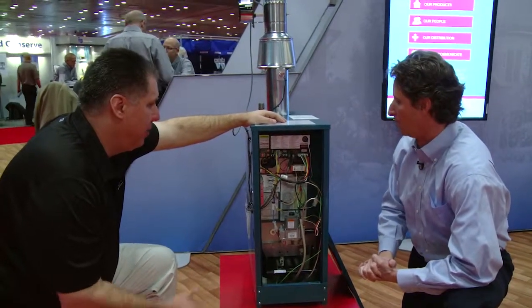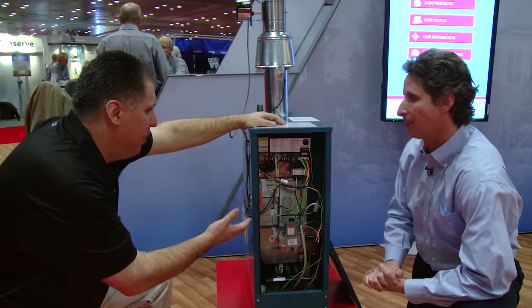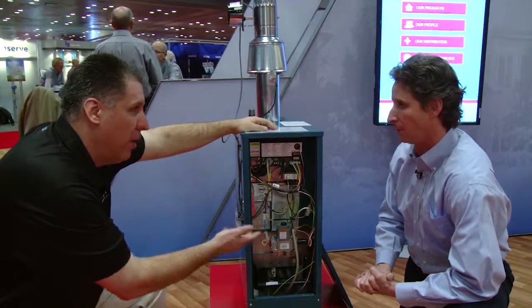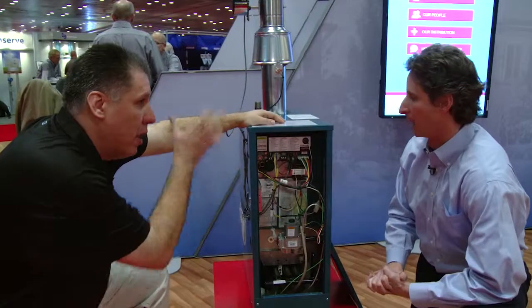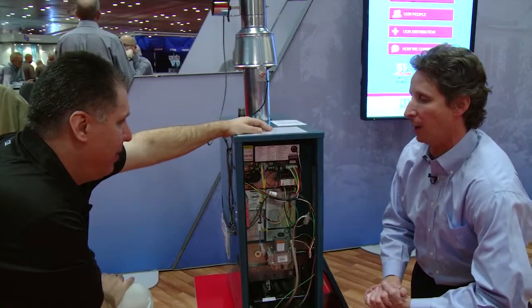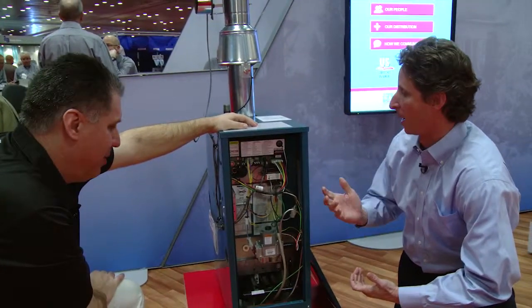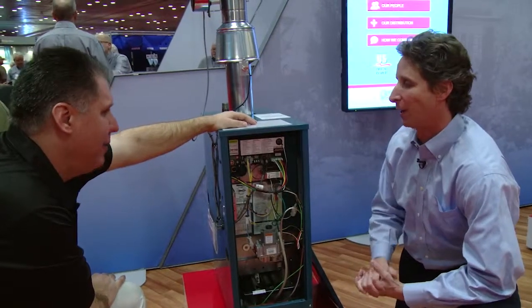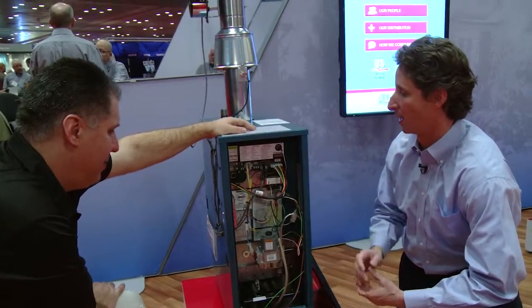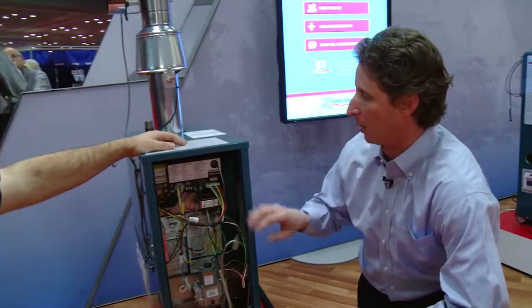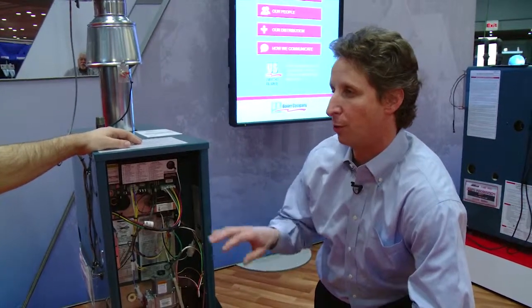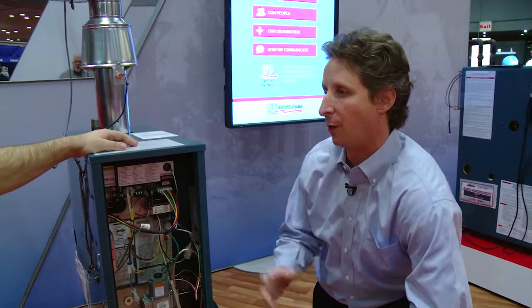Hey Chris, if I heard you right regarding the zoning, I can zone with 2 pumps, or zone with a pump and 2 zone valves, is that accurate, with no external equipment? That's exactly right. If you had to go add an extra relay for an extra zone, I'm not sure what that costs you, but again, we've tried to save the contractor time and money, giving him all the information he needs, as well as allowing priority for the indirect water heater if you have one on the job.